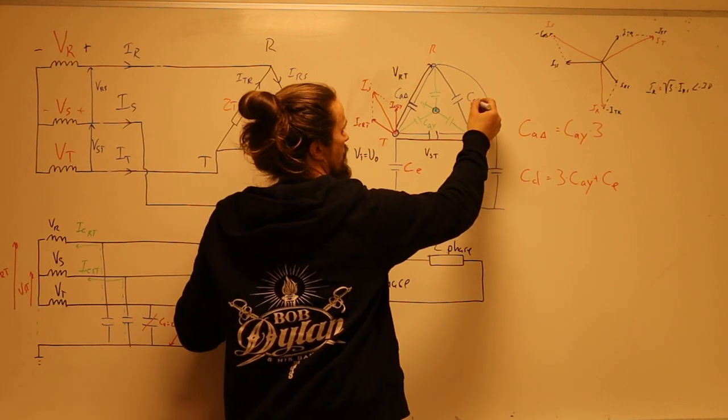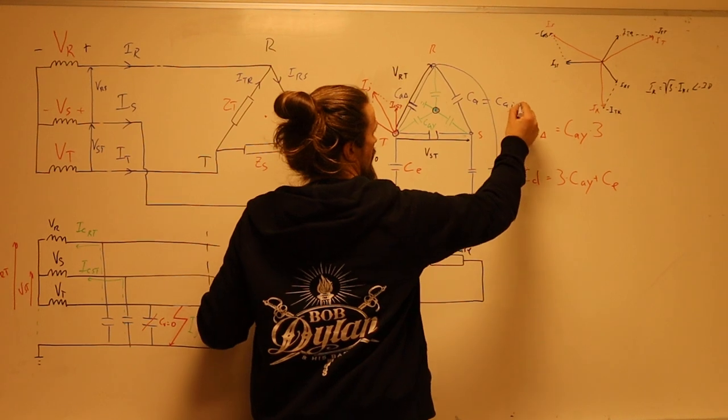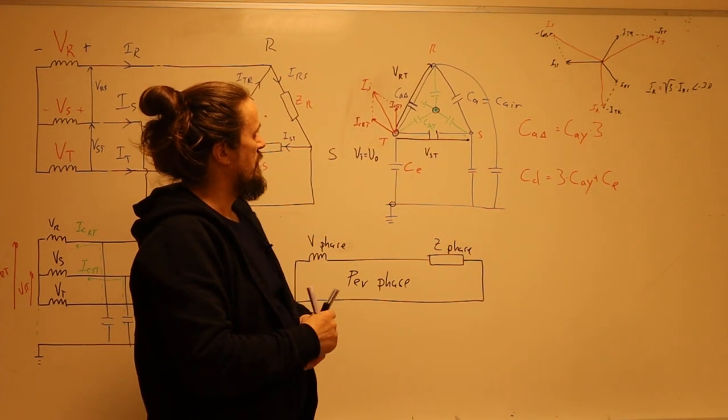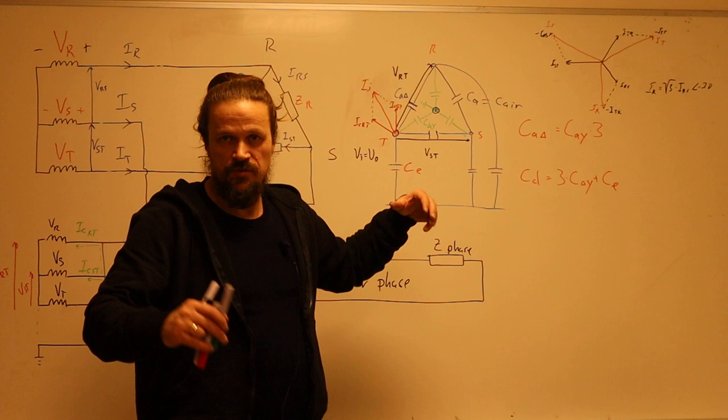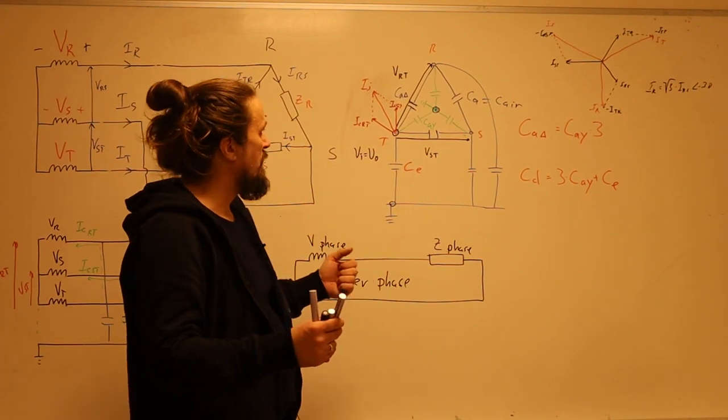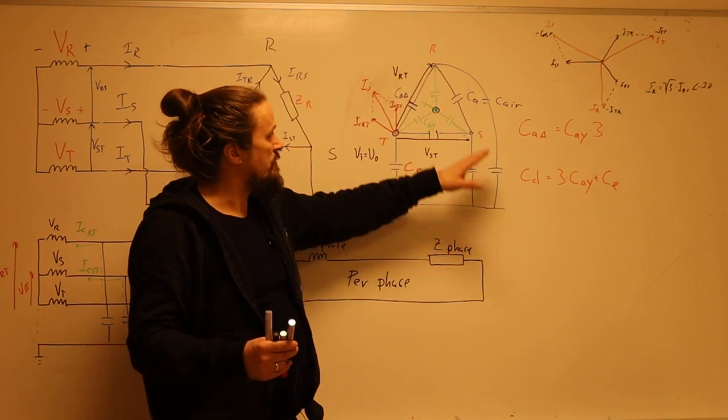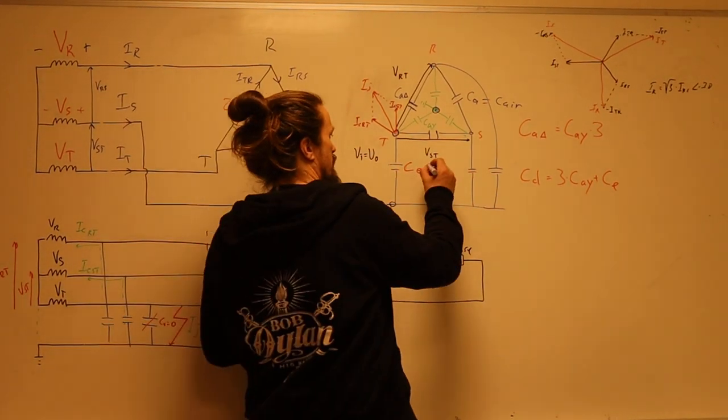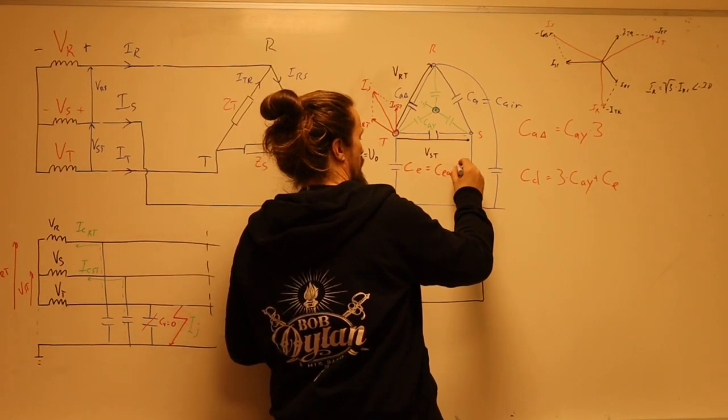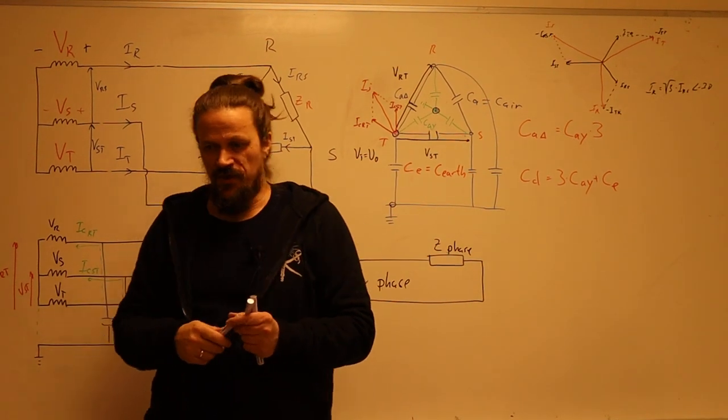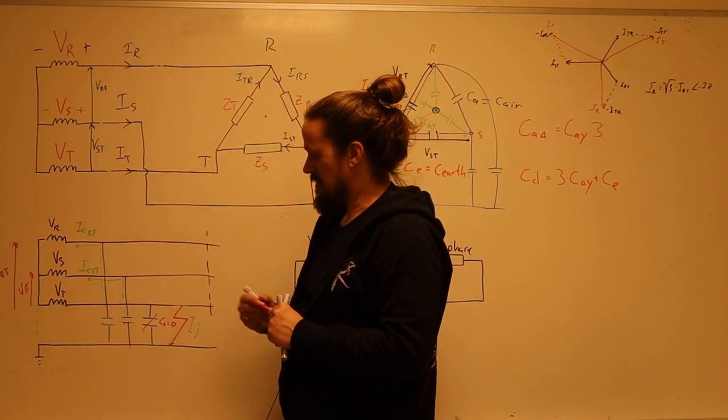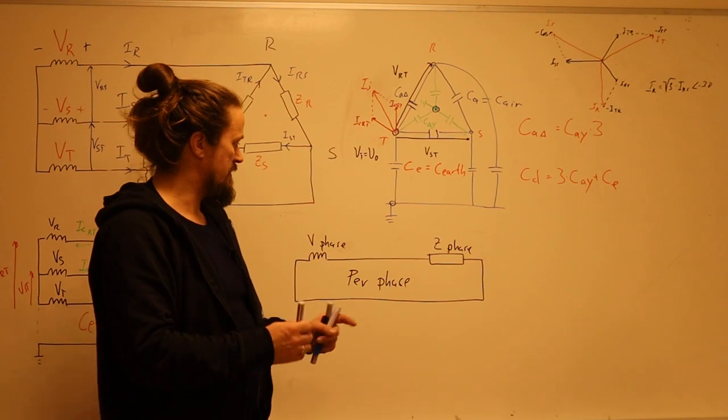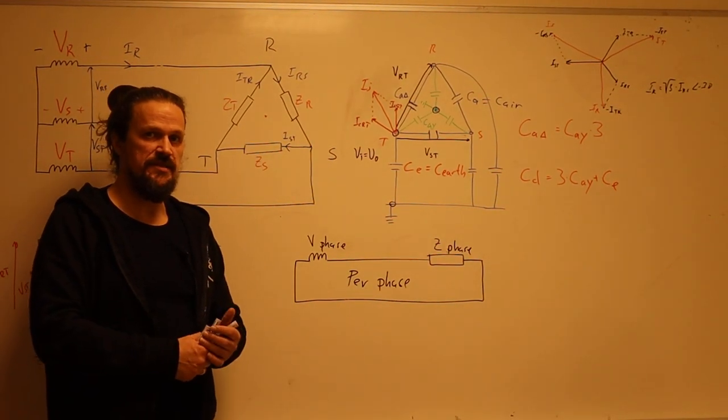That is what we call ca which also is c air, so it's the capacitance in air between the lines, and that is easy for us to compute because we know the distance and we can then know the capacitance. There is also a potential from the lines down to earth, and that's the ce. The ce is c earth, capacitance to earth. When we have these capacitances to earth, this is the ce that is represented in this per phase directly since it's a per phase quantity.